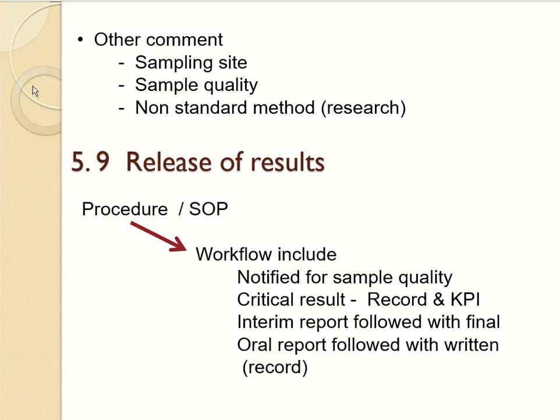So under clause 5.9, it mentioned release of results. The lab should have a procedure or SOP for the workflow of releasing results, which includes notification of sample quality. Maybe the sample is good, or maybe the sample is lipemic, icteric, or hemolytic. So it should be noted in the result. If there is a critical result, it should be recorded, and this critical result actually needs to be informed to the user, the doctor, as soon as possible. So when we notify the doctor, we should record it, and it is actually one of the KPIs in the lab that should be monitored and maintained. And there should be a procedure for an interim report followed by a final report, and an oral report should also be followed by a written report.